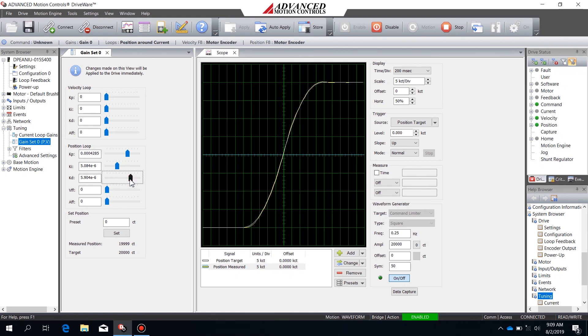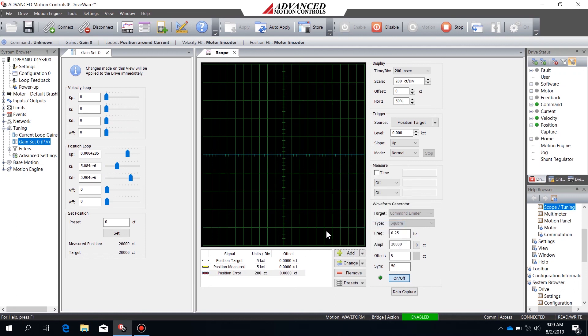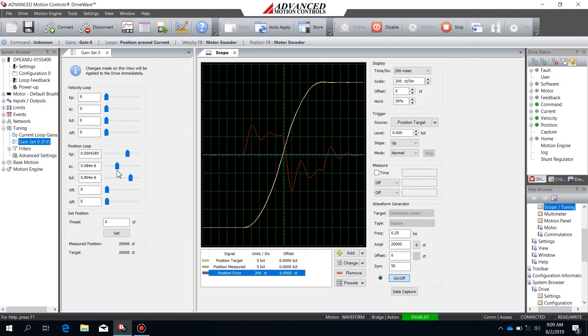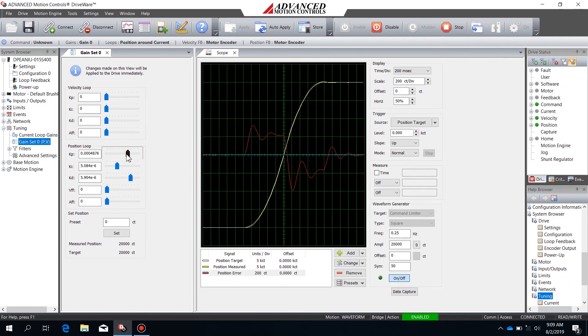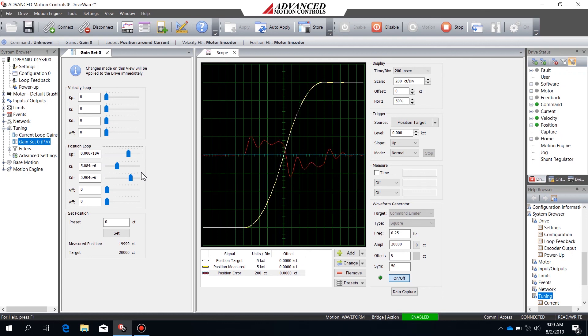Once I get a fairly tight tuning after going back and forth a few times, I'm going to add the position error signal to look in more detail at the error in this move profile. In my case, there may be a little more error than I'd like, so I'll keep increasing the proportional and derivative gains until the error is a little bit smaller. Once I've got a response that's pretty good, I can keep increasing if I want. Fundamentally, the process of tuning is just getting the system to respond within prescribed requirements, so I can keep increasing gains until I'm satisfied it's good enough for my system.